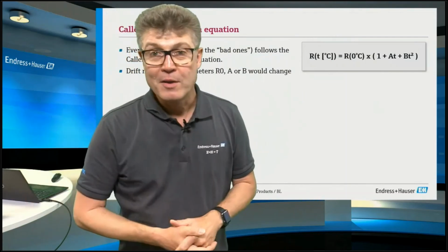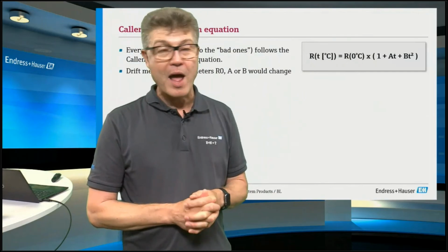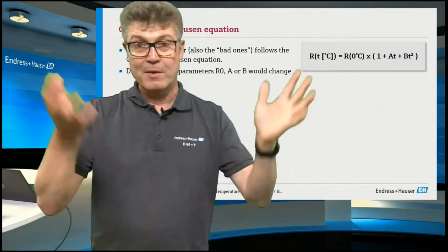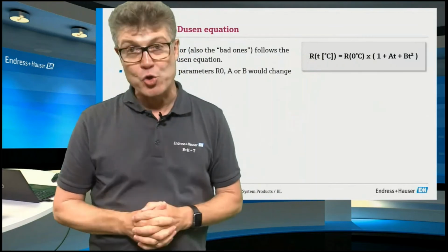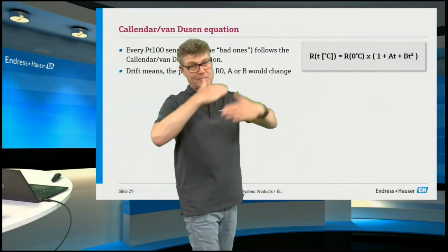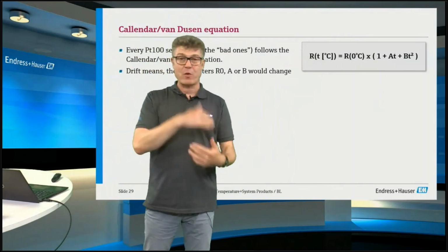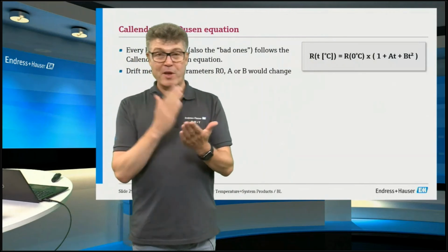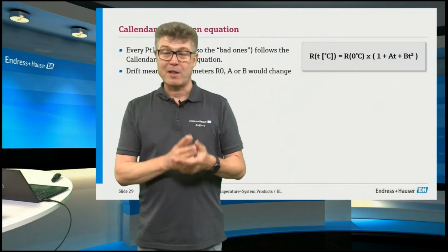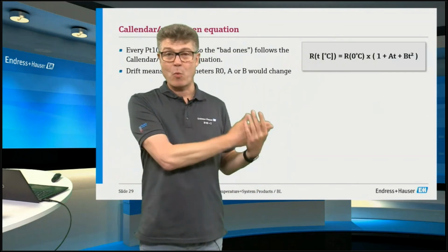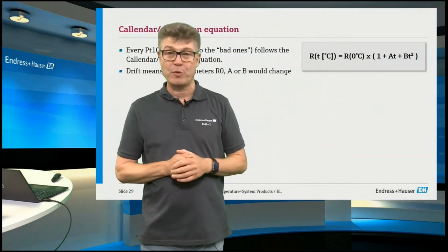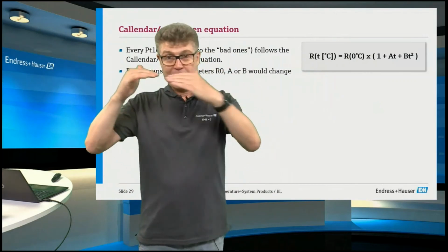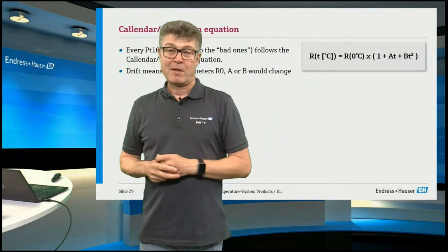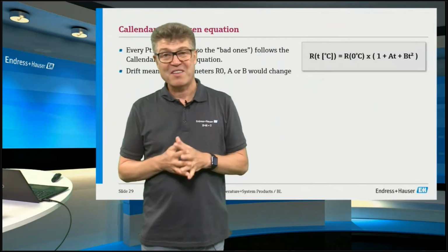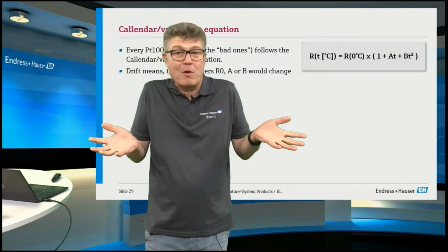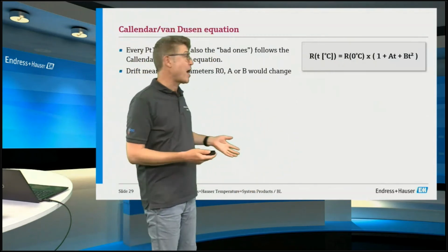So the watchdog is barking, making an alarm and says, oh, I have found a mistake. Dear user, what should we do? And you can also convert this the other way around. If the calibration is right, and it was right yesterday and the day before and the 100 days before, from the day it was produced in the calibration lab, there was no deviation in this 1-point calibration, it must be good also now.